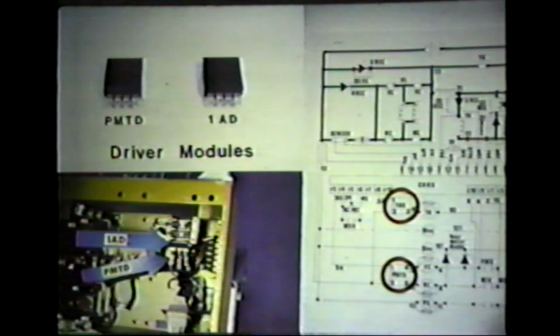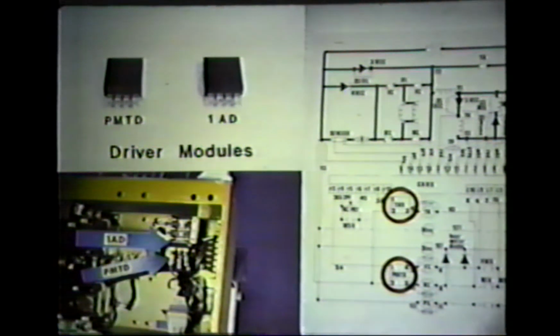2 fault detector modules labeled PMTD and 1AD are wired in series with the contactor coils. They control current flow through the coils in conjunction with the control card's pulse monitoring trip circuit. If the card sees a runaway speed control fault, it will turn off the driver, which in turn opens the contactors.